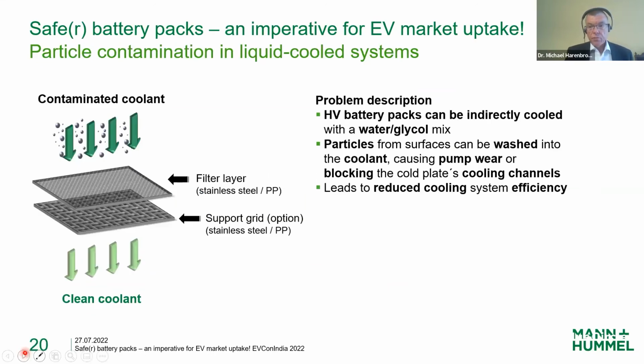What's important is that even if you have a liquid cooling system, you need to make sure it operates properly. Especially if you have particles in the system, this can create severe problems. It's a closed system, so you might wonder where those particles come from, but they can stick on surfaces of the components the cooling system is made from, like the cooling plate or heat exchangers. If those particles are then washed into the system, they can create pump wear, especially if they're mineral or metal particles.